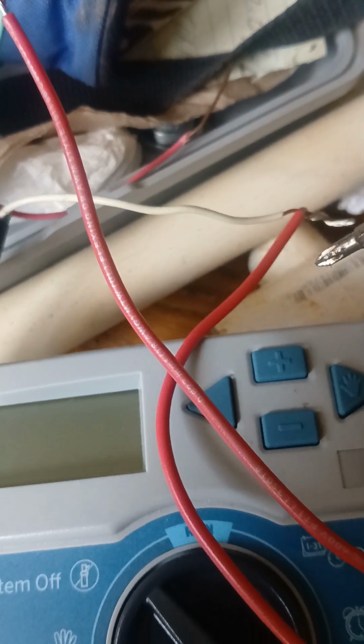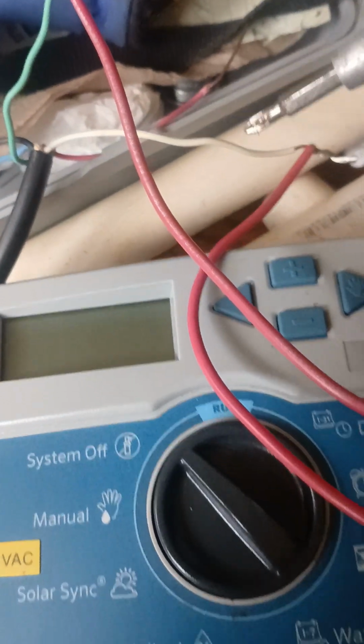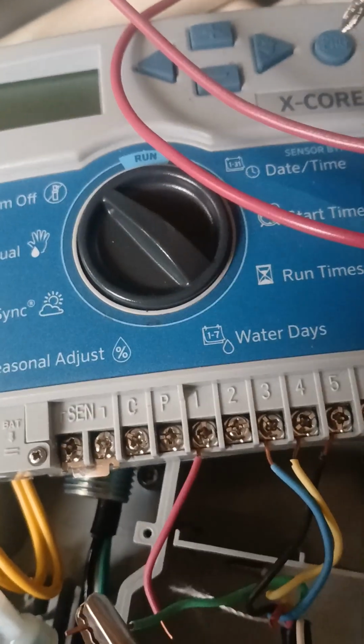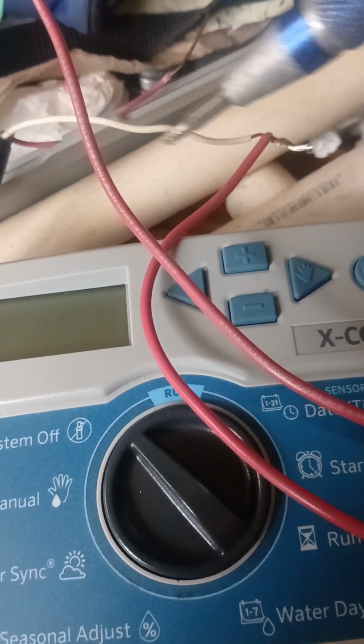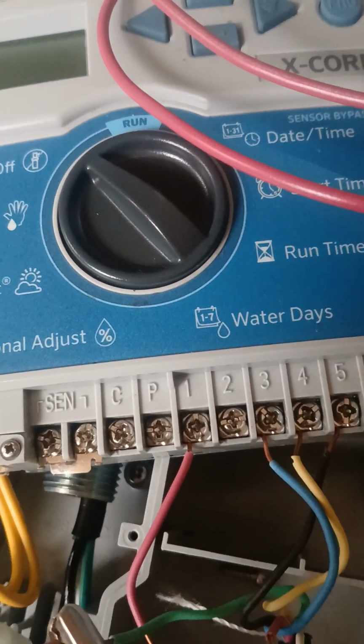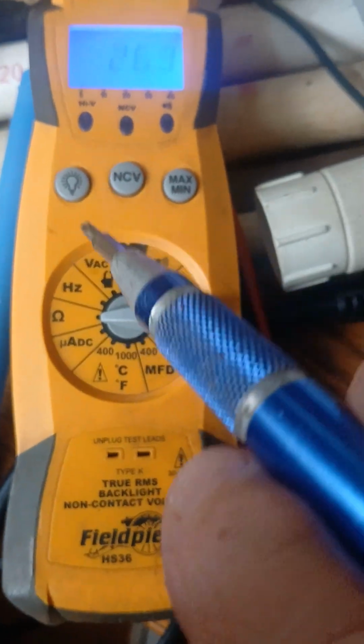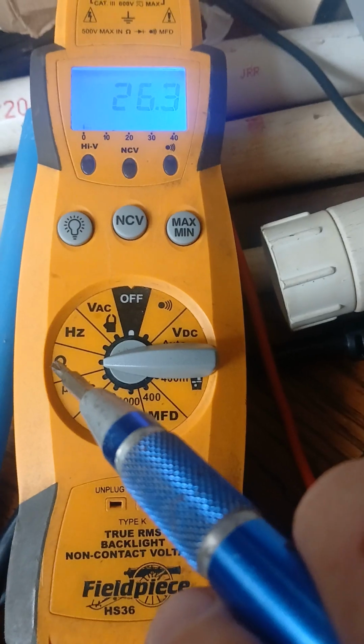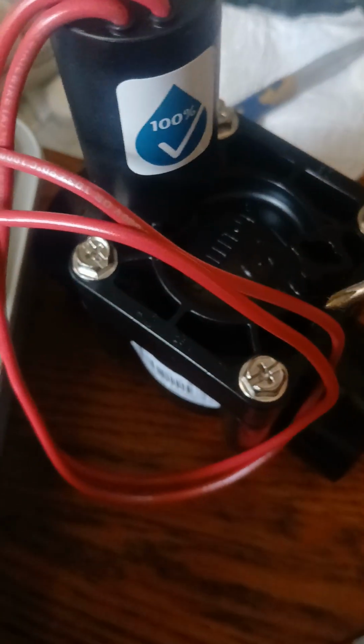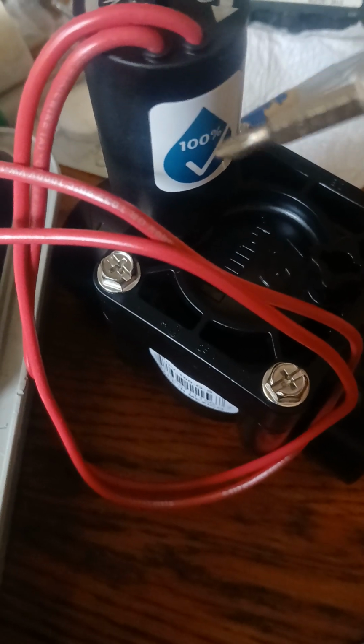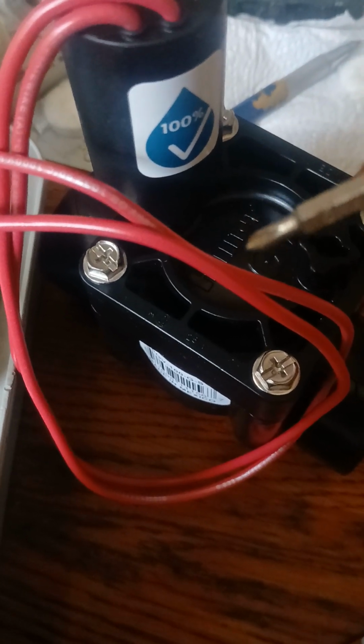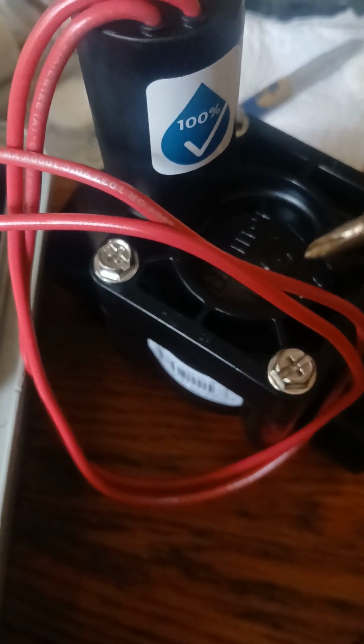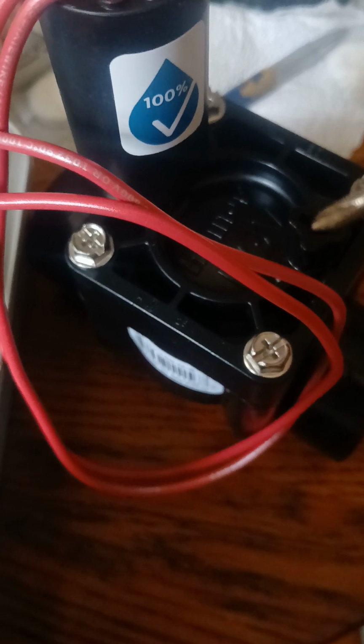So we have it tied here and here. Do keep in mind, this would already be connected after the install. It should be connected in the yard somewhere, so one may not have to do this. I'm not sure if you would have to go through all this rigmarole. But we take the meter and put our multimeter in the ohms position. A good solenoid, a good valve, may read between 20 and 60 ohms. Again, to reiterate, a good valve may read between 20 and 60 ohms.